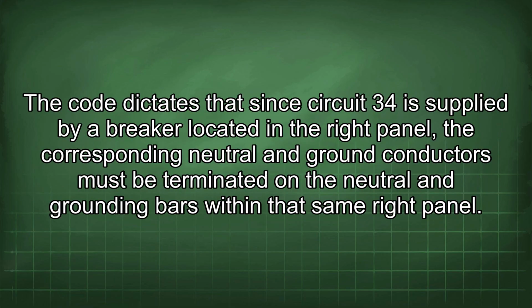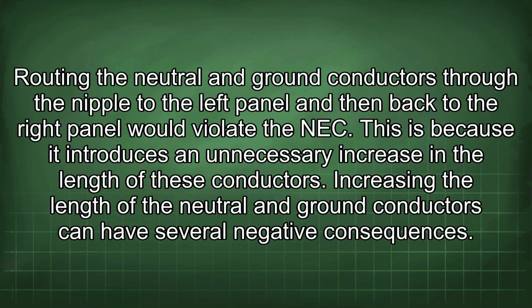The code dictates that since circuit 34 is supplied by a breaker located in the right panel, the corresponding neutral and ground conductors must be terminated on the neutral and grounding bars within that same right panel. Routing the neutral and ground conductors through the nipple to the left panel and then back to the right panel would violate the NEC. This is because it introduces an unnecessary increase in the length of these conductors.